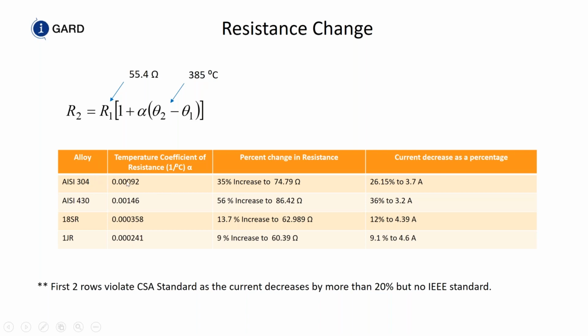If you use 304 stainless steel, you get a 35% increase in resistance from 55 ohms to 74.8 ohms. 430, it increases 56%. 18 SR changes by 13.97%, and 1 JR changes by 9%. Conversely, the current decreases over time because the temperature is higher. So when you get to 75 ohms from the initial 55 ohms, we went from 5 amps to 3.7 amps with 304. For 430, we're down to 3.2 amps. So imagine we started at 5 amps, we're down to 3.2 amps, and this is a continuously rated resistor. 18 SR, we're down to 4.39, and 1 JR, we're down to 4.6.